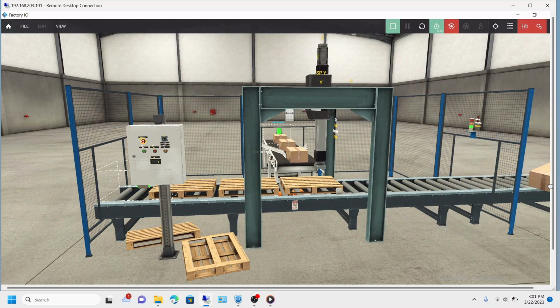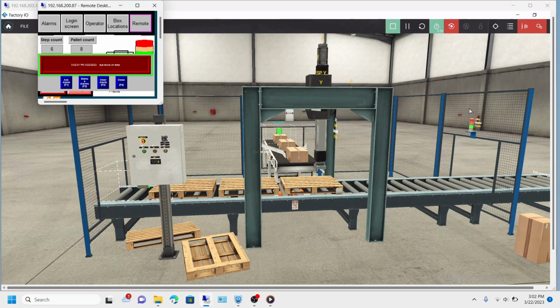we're gonna take the box out of the way. Well, it dropped the box, it doesn't know where it's at. The system is physically stuck. So this one takes more time to do. It takes about 6 seconds before the alarm will go off. This just allows a couple different watchdogs over various systems to fix itself as needed, but this one does not, because we don't want to squish a box if it is out of the way.